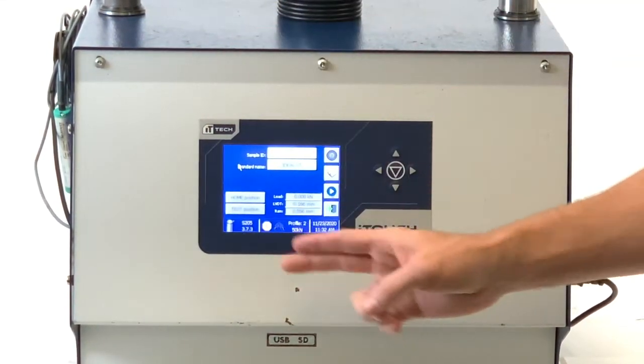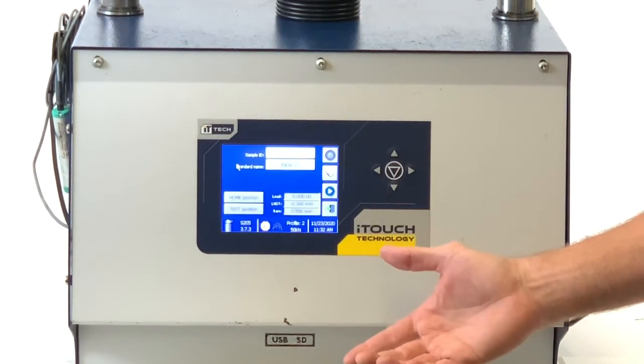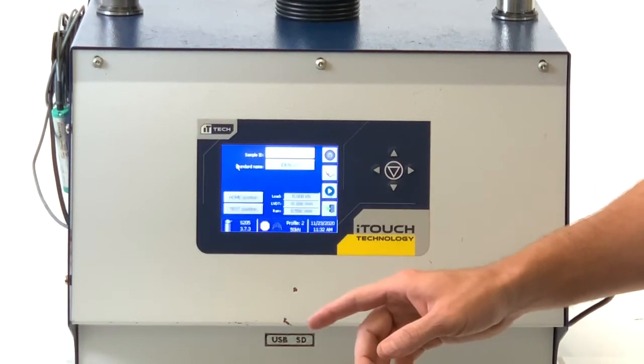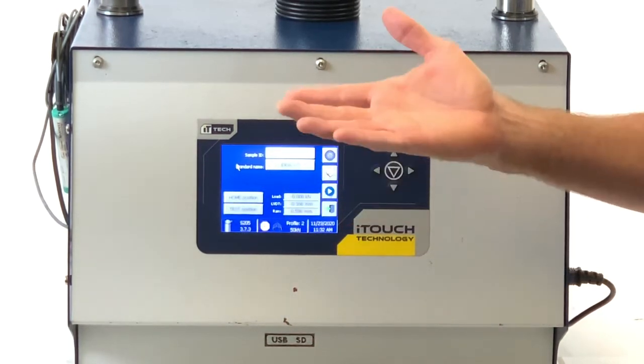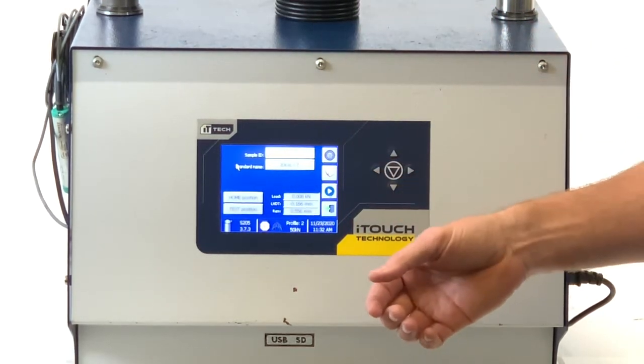There are also two more important buttons on the home screen: the home position, which is the resting position for the load frame when not in use or when you're done with the test, and the test position, which is a predetermined height the RAM will rise to in order to properly run your Ideal CT test.